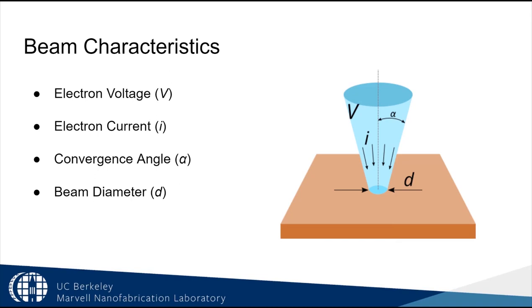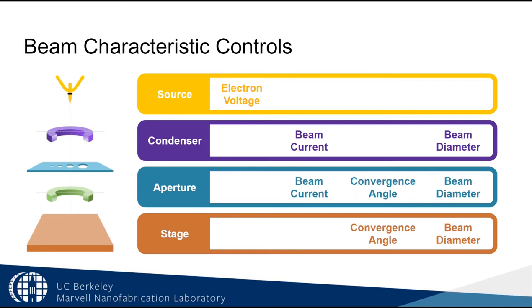To change the size of that cone of electrons, we need to control the electron voltage, the number of electrons in the cone, the convergence angle alpha, and the diameter of the cone when it interacts with our sample. We make various choices with the SEM mechanics to control these parameters. Understanding why we make certain choices will help you get the images you want for your research. There are four SEM components that let you control the beam characteristics: the source, the condenser, the aperture, and the stage.